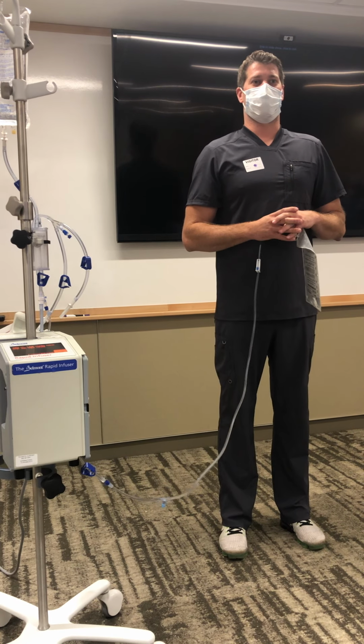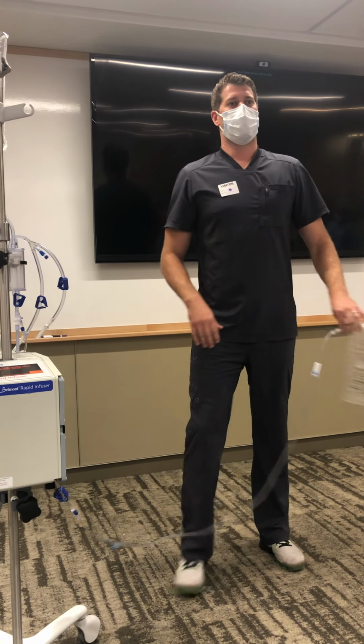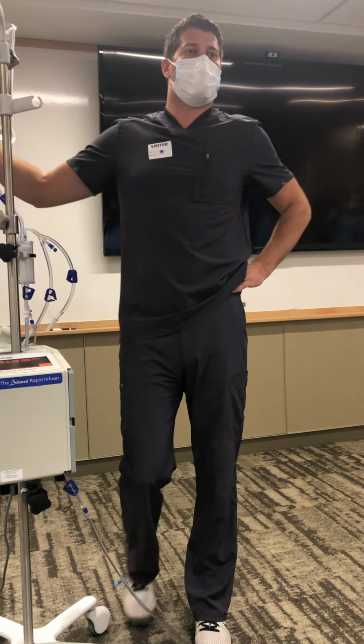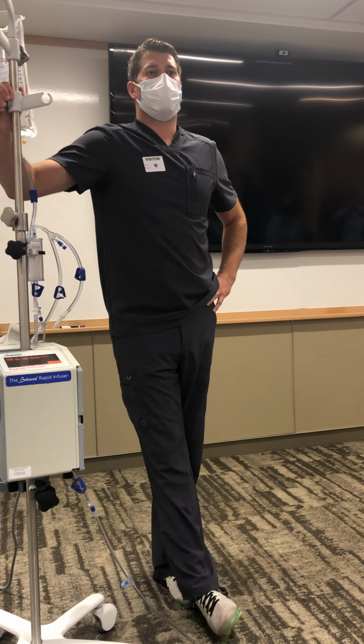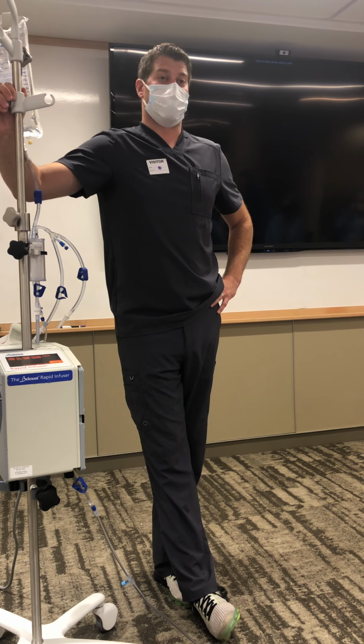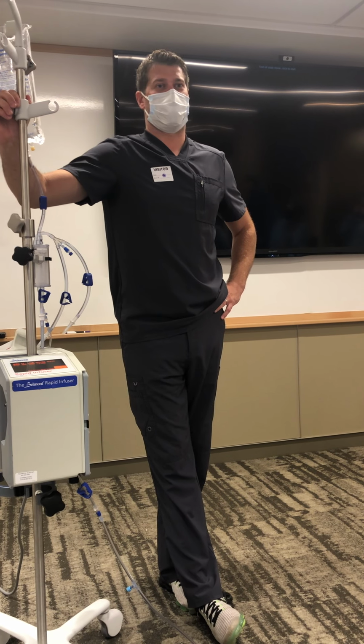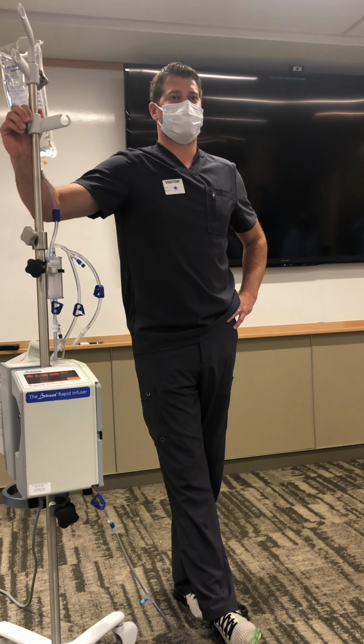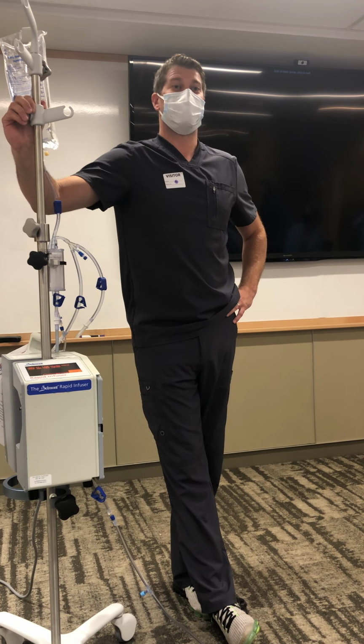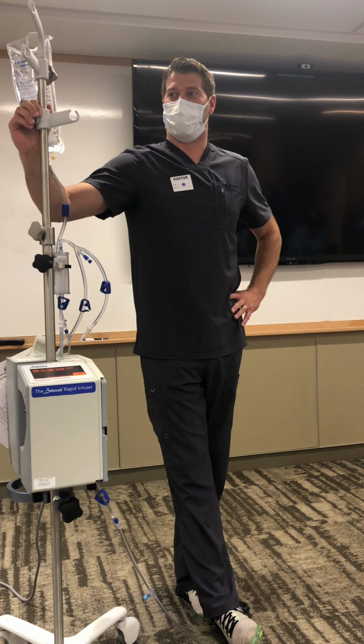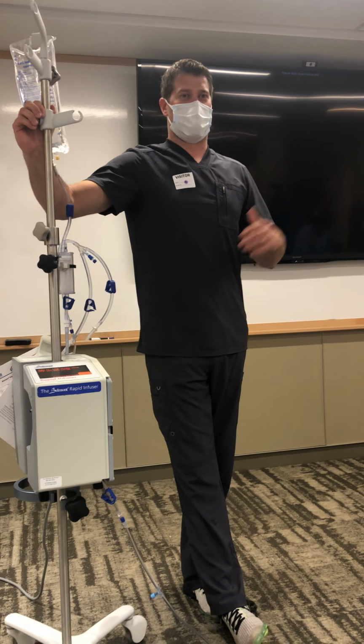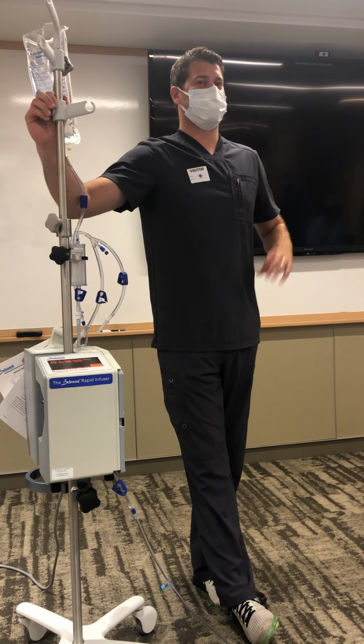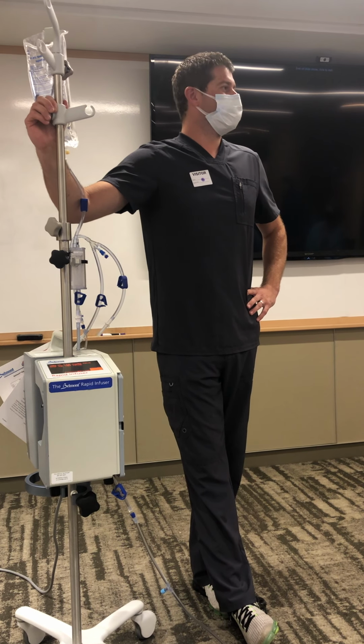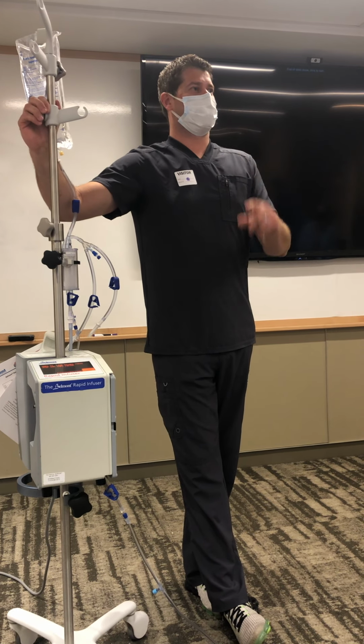Any questions to this point? So you put the cartridge in the machine before you turn the power on. If you turn the power on first, will it affect anything? It'll give you an alarm, because anytime the door's open and the power's on, it'll start beeping. That's what I was going to say. Most of us turn the machine on first, and that makes sense for a lot of other equipment. For this one, just load it up dry, power off, smooth sailing. Any other questions? I think I saw another hand.